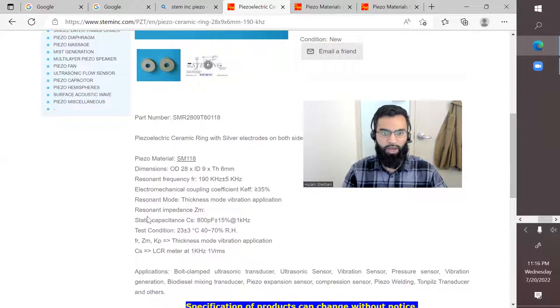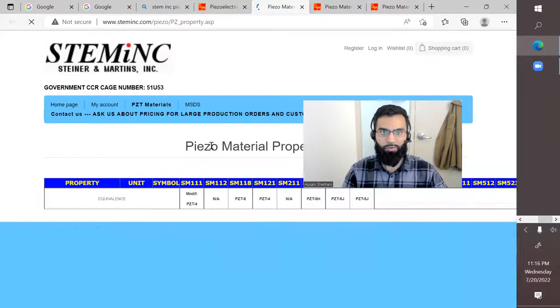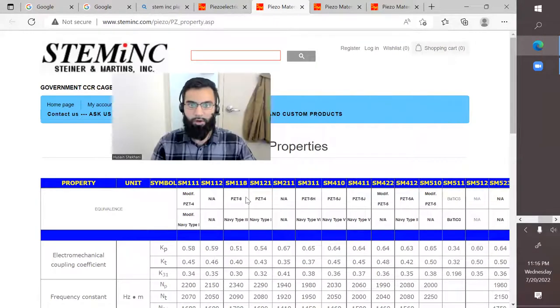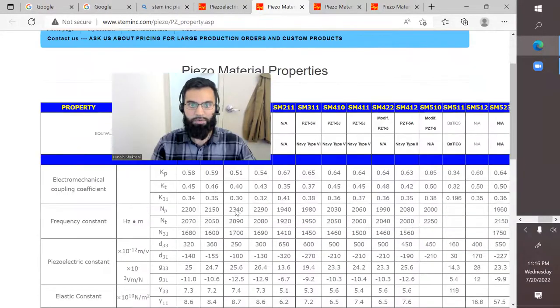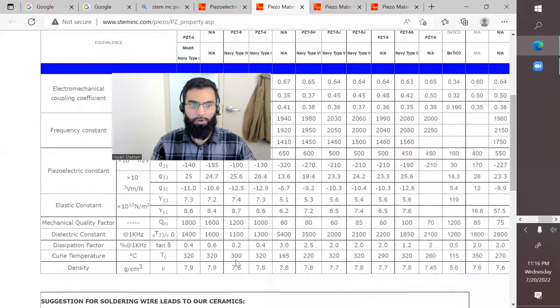Here are things you can test, like the static capacitance, to make sure you're getting the right product. You can also ensure that if you get this ceramic 118, which is that same PZT-8 material, you can test the dielectric loss factor with an LCR meter. You can test for the capacitance, and from a parallel plate capacitor standpoint, you can determine the permittivity.